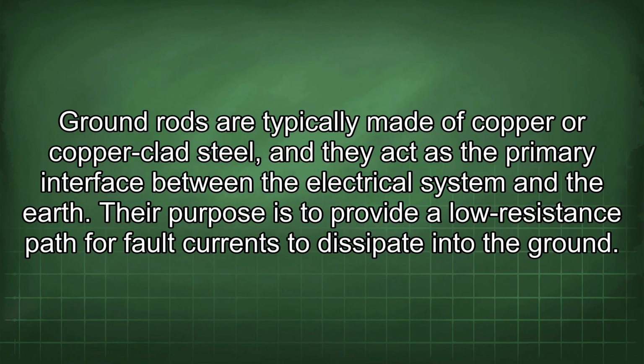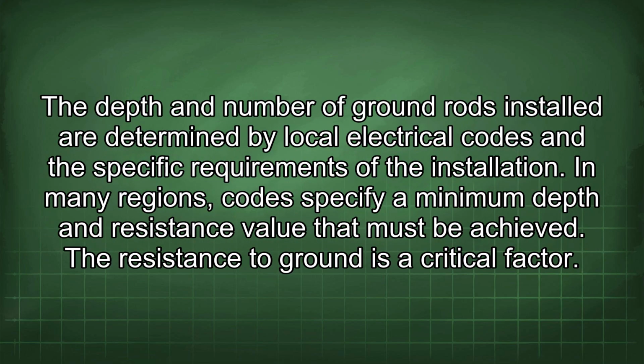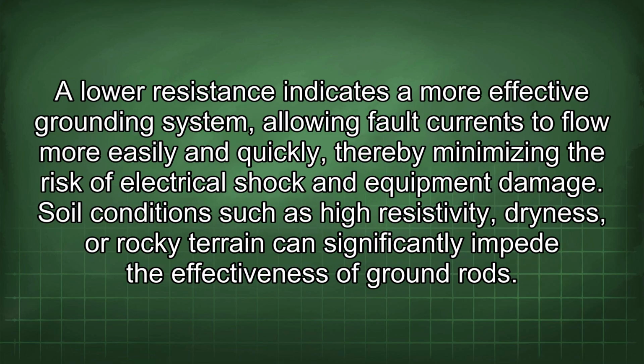Ground rods are typically made of copper or copper-clad steel, and they act as the primary interface between the electrical system and the earth. Their purpose is to provide a low resistance path for fault currents to dissipate into the ground. The depth and number of ground rods installed are determined by local electrical codes and the specific requirements of the installation. In many regions, codes specify a minimum depth and resistance value that must be achieved. The resistance to ground is a critical factor. A lower resistance indicates a more effective grounding system, allowing fault currents to flow more easily and quickly, thereby minimizing the risk of electrical shock and equipment damage.